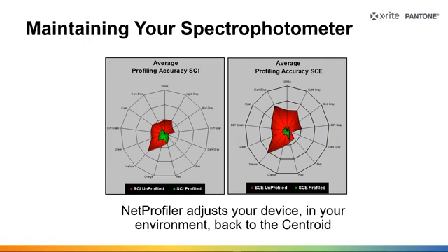And one of the things that's really key is Net Profiler is not only correcting this because of drift and dirtiness and things that might be going on with your instrument, but maybe most importantly, it's doing it, as it says here, in your environment. Because when we produce an instrument and test it for inter-instrument agreement and all those kinds of things, our production facilities are an extremely tightly controlled environment. It's 72 degrees plus or minus 1 degree in there, right? The humidity is controlled very tightly. So it's a really tightly controlled environment.